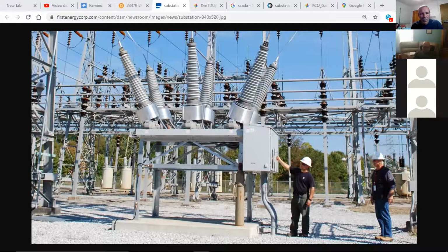And you can actually see the wiring harness that comes off here, and it's going down to the control panel for this one phase, phase A, phase B, phase C. All right, it's going into the control panel. Now he said RTU or PLC interface. Like I said before, we usually use RTUs. So I'm able to come in here and get actual readings if I need to. I'm able to open and close the breaker from here also.